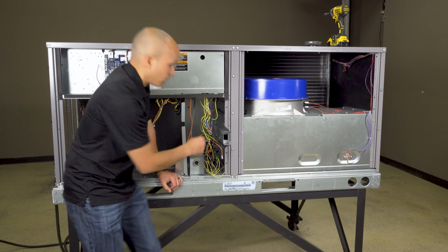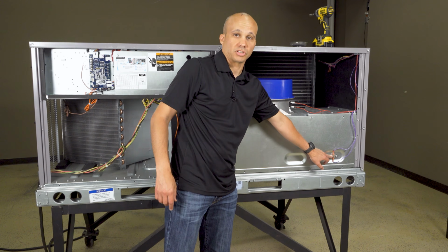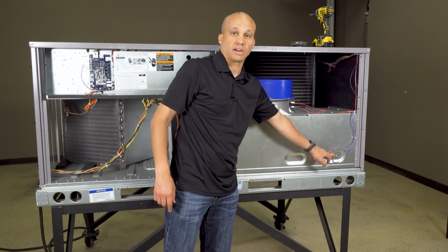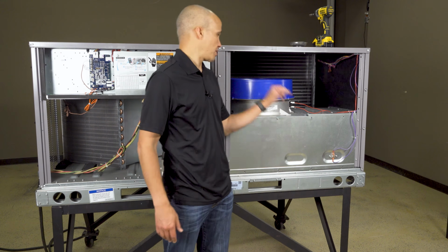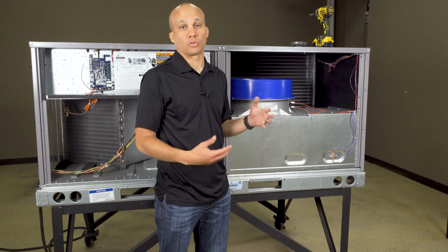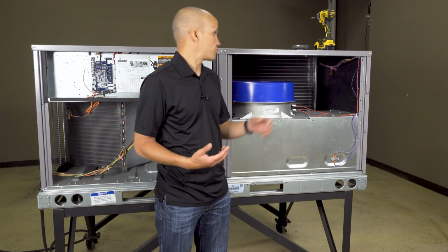We also have in here a limit switch over here on the heat exchanger. And when I open up this cabinet here, you'll see the heat exchanger. That guy's job over here is if it gets too hot in here, shut it all down. That would be because this fan broke, or if it's an older style fan with a belt-driven motor, maybe the belt broke, or maybe there's something in the ductwork obstructing it.